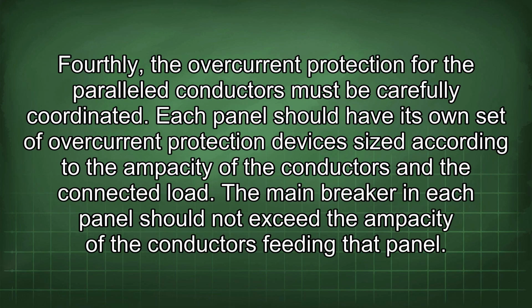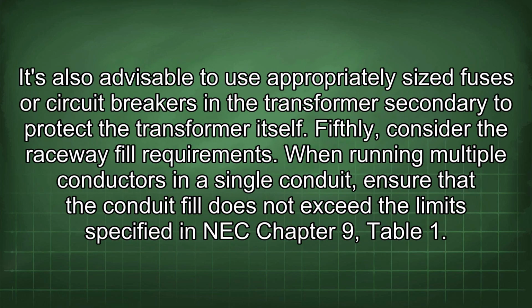Fourthly, the overcurrent protection for the parallel conductors must be carefully coordinated. Each panel should have its own set of overcurrent protection devices sized according to the ampacity of the conductors and the connected load. The main breaker in each panel should not exceed the ampacity of the conductors feeding that panel. It's also advisable to use appropriately sized fuses or circuit breakers in the transformer secondary to protect the transformer itself.